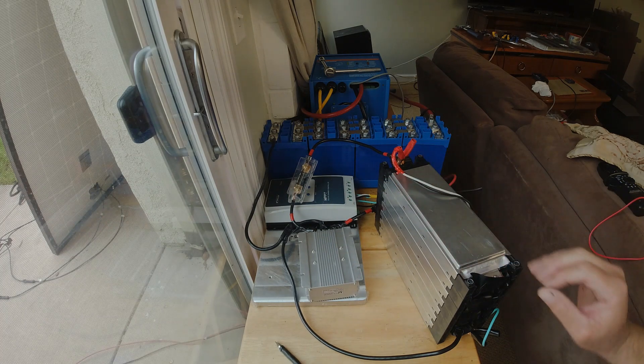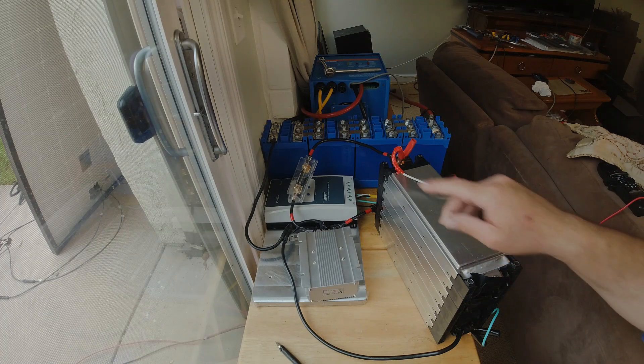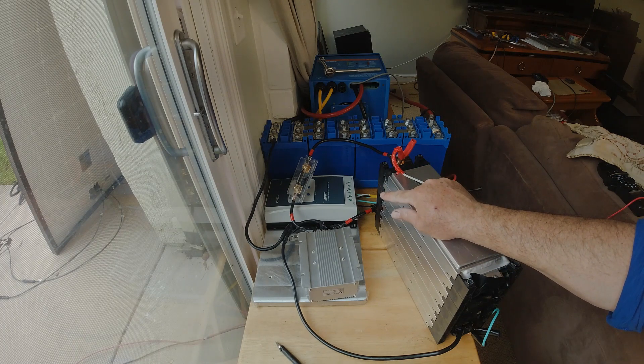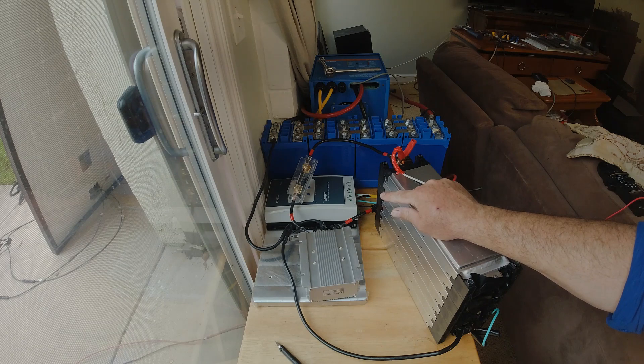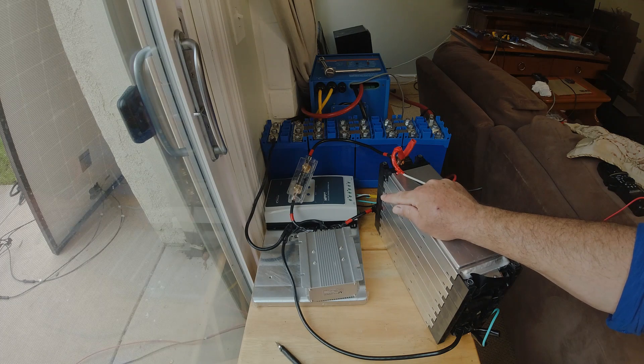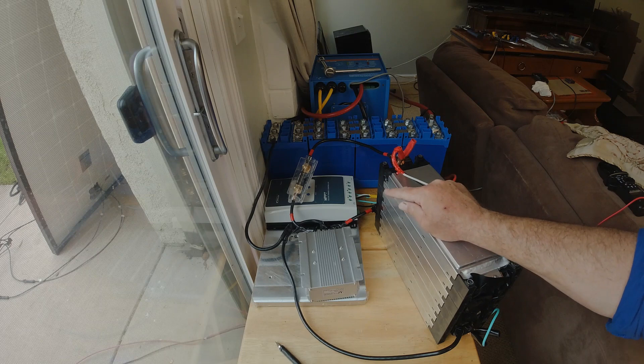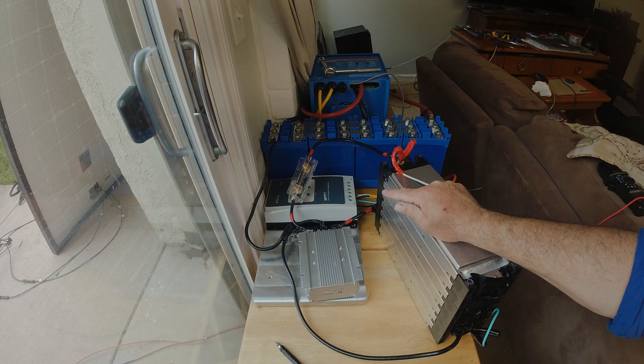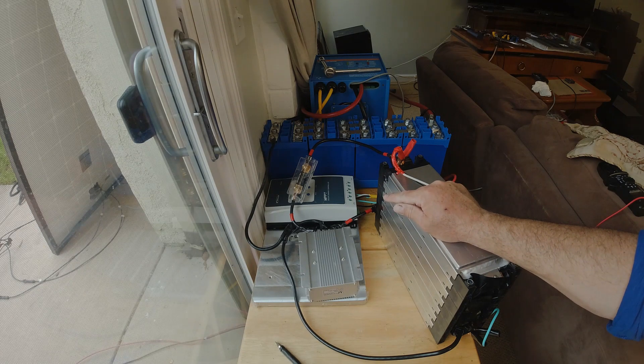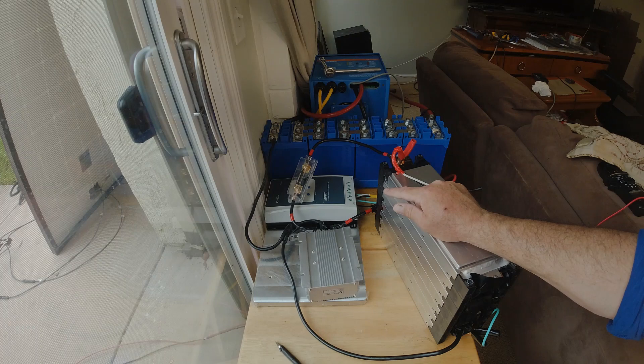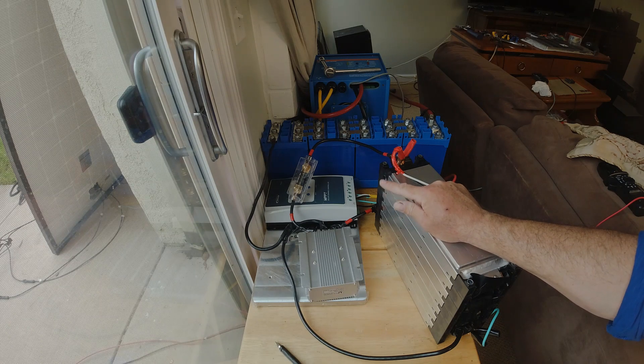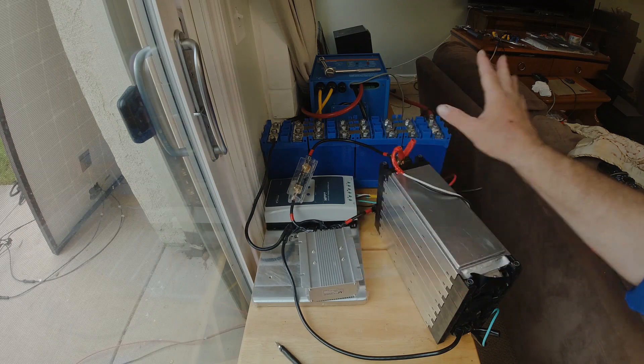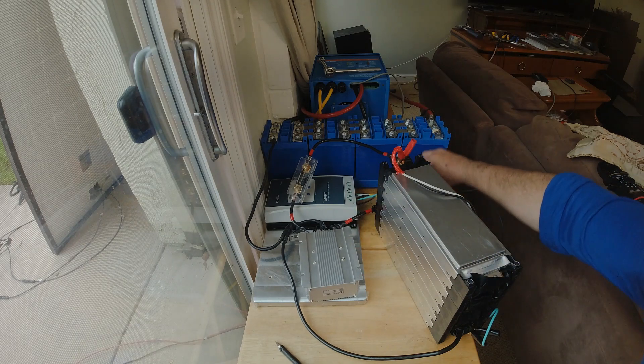All the charge controllers as far as I know will do at least 12 and 24 volt and they sense that automatically. This one does 12 and 24 volt, so you just take the 12 volt values and double them. When you're going to switch, you actually need to de-power everything - disconnect the batteries, disconnect your solar.